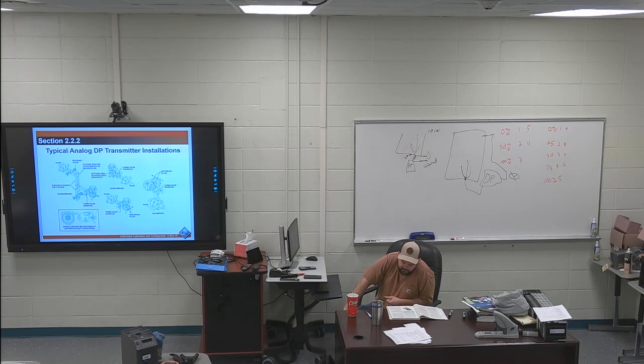Open vessel installations for level measurement. So this will be literally like what you're going to do in the lab. That's open vessel, so that means it has an open top, open atmosphere is what it means. Second paragraph, first sentence. So last paragraph on page 13. If the transmitter is mounted below the physical minimum point of the desired level range of the tank, a zero suppression calibration must be performed.